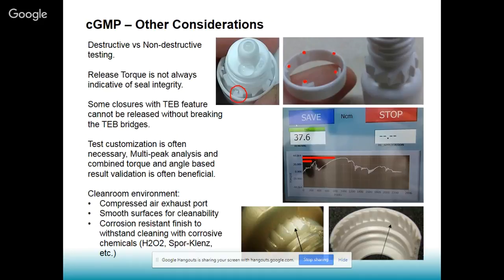I also wanted to call out that in a clean room environment, some of our machines are more optimized for it with the stainless steel enclosure, and we have a compressed air exhaust port specifically, or we can also put a filter on that port, so we don't just exhaust the incoming air into the clean room environment, but we exhaust it through a fine filter. And we provide on most of the machines smooth surfaces for cleanability. And I also like personally to check the corrosion resistance with the customer specific cleaning chemicals. Some of them can be very demanding.